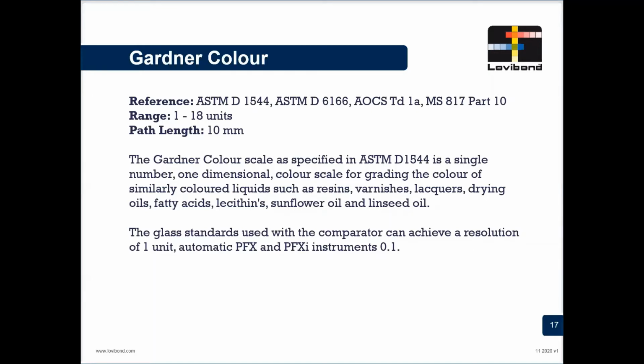But when we go down to that level, we have to be aware of the tolerance range we might get on our measurements. Although we can measure to 0.1 of a unit, our actual tolerance on the product when doing the measurement may be something like 0.2, 0.3. So you have to be careful balancing your tolerance against the resolution the instrument can measure.